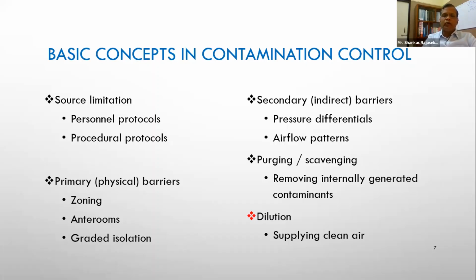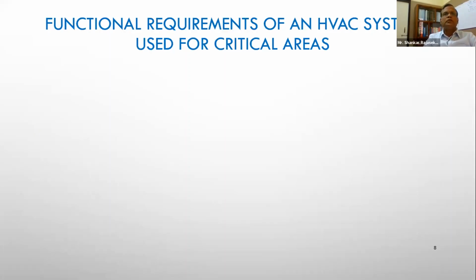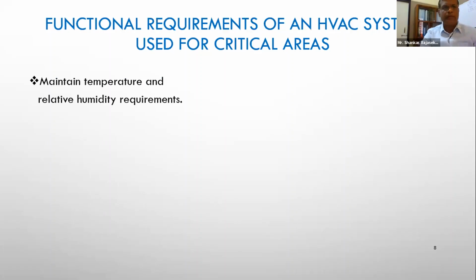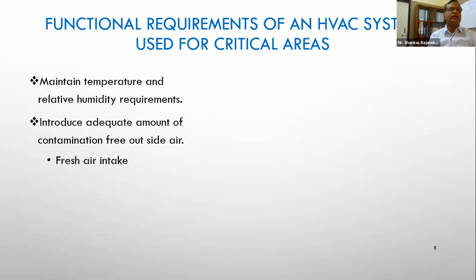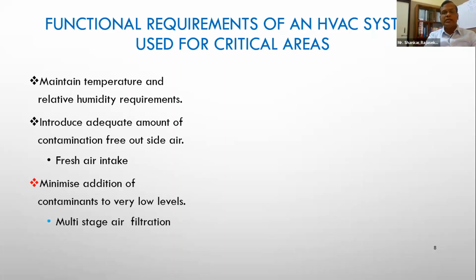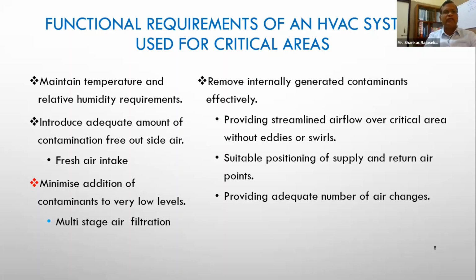And then, of course, we also spoke a little in the earlier slide about dilution. That is by supplying clean air and then ensuring that the contaminants are getting diluted. So we need to apply as many as possible of what we see on the screen, so that we will be able to have maximum control on infection spread. So what are the functional requirements of a HVAC system used in critical areas? Of course, we maintain temperature and relative humidity requirements. That's for comfort as well as from the infection prevention angle. Introduce an adequate amount of contamination-free outside air, for dilution of the several gaseous pollutants that could be generated inside. Minimize addition of contaminants to very low levels through multi-stage filtration.